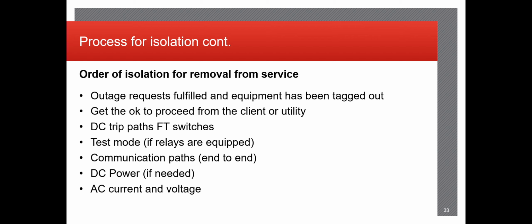And there's an order of operations for the process of isolation of equipment. For example, let's say we're taking a relay out of commission for however long. The relay test switches will be opened in a specific order, and that is because you want to avoid having anything in that could operate a piece of equipment that you do not plan on taking out of service. First of all, you want to verify that your outage request is fulfilled and you can start the procedure. Get the okay from the client or utility.